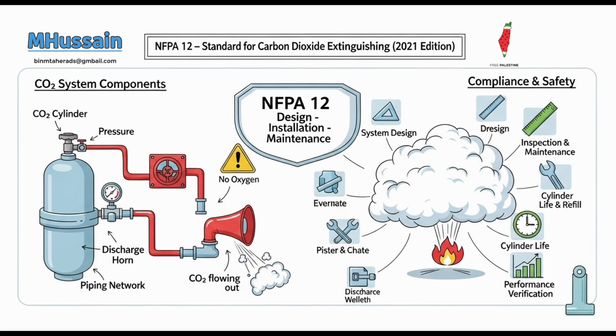However, automatic release is permitted for spaces of 6,000 cubic feet or less, provided several stringent conditions are met. Okay, smaller spaces can be automatic if. There must be horizontal egress to an open deck, meaning a clear path directly outside. The enclosure must be unmanned during operation, the system must be locked out when personnel are present, and crucially, the automatic actuation cannot interfere with the safe navigation of the vessel. Strict rules. Path out, unmanned, locked out, doesn't affect steering. Exactly.